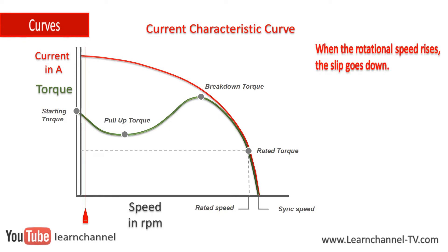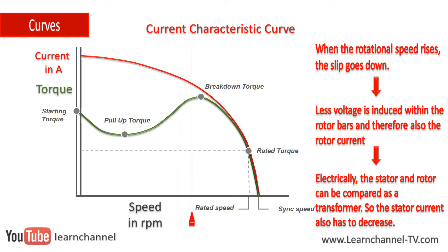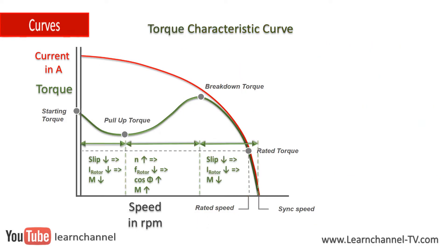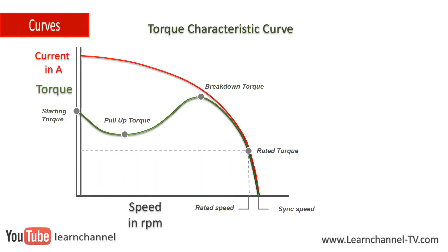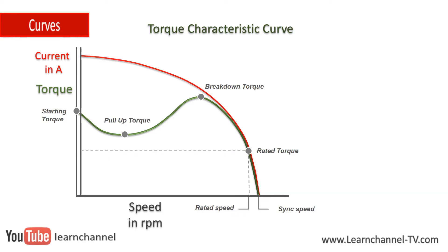As the rotational speed increases, the RMF cuts the rotor at a lower frequency and the motor current decreases inevitably. Several effects determine the course of this characteristic curve. Once the three-phase asynchronous motor has reached its nominal speed, it can safely maintain its nominal speed even with increasing load, because the torque curve is steep at the nominal point.